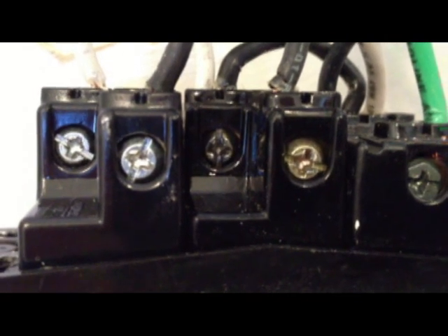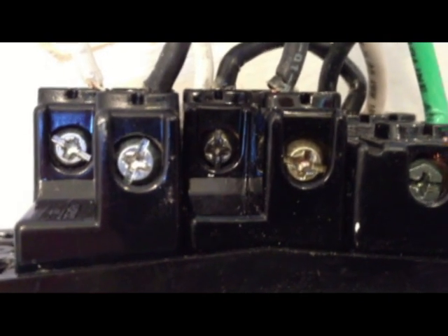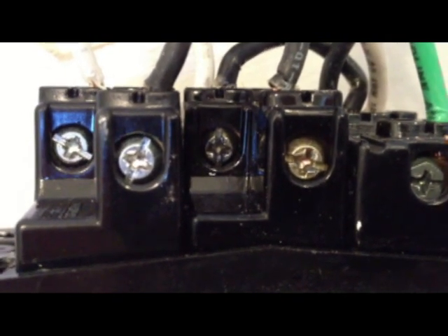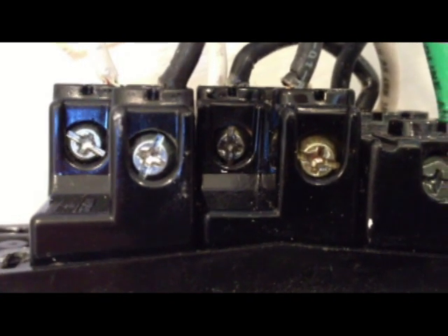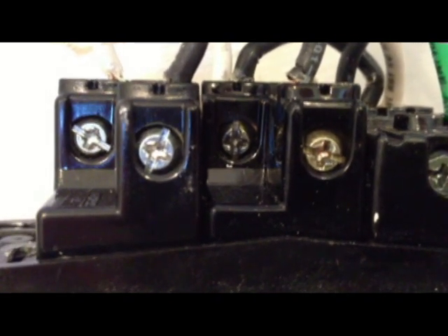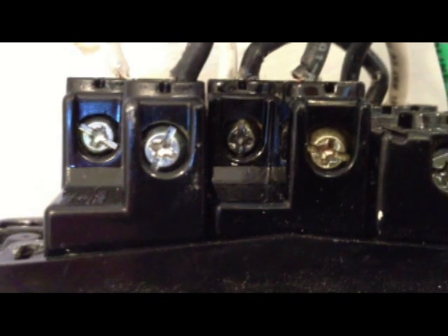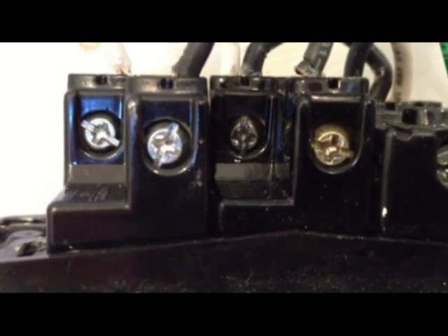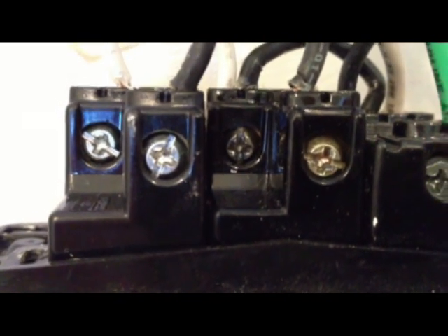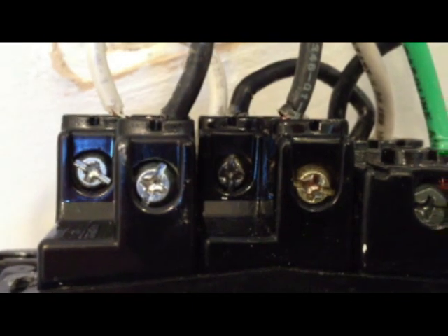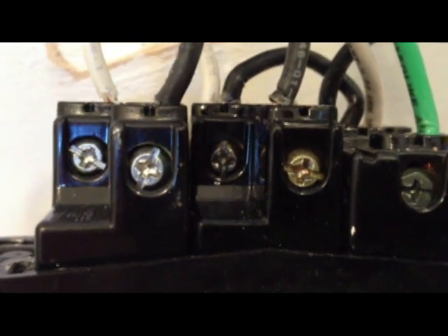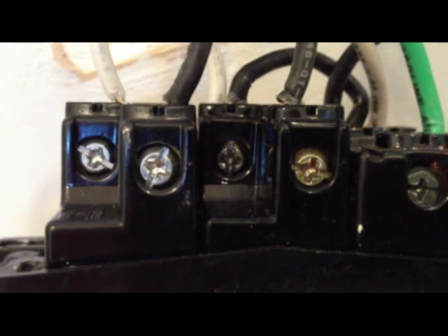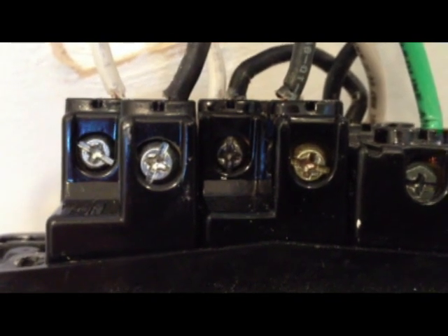Okay, I'm ever more convinced now that the middle switch is bad. Can you see how it's discolored? And the two on the left there are nice and bright and silver. That one's discolored, and it shouldn't be. It should be the same color as the two on the left. So I've got a bad switch here. I re-terminated those wires, snugged them down nice and tight, and now the middle switch doesn't work at all. So I'm going to have to go find myself a new replacement switch and get this problem solved.